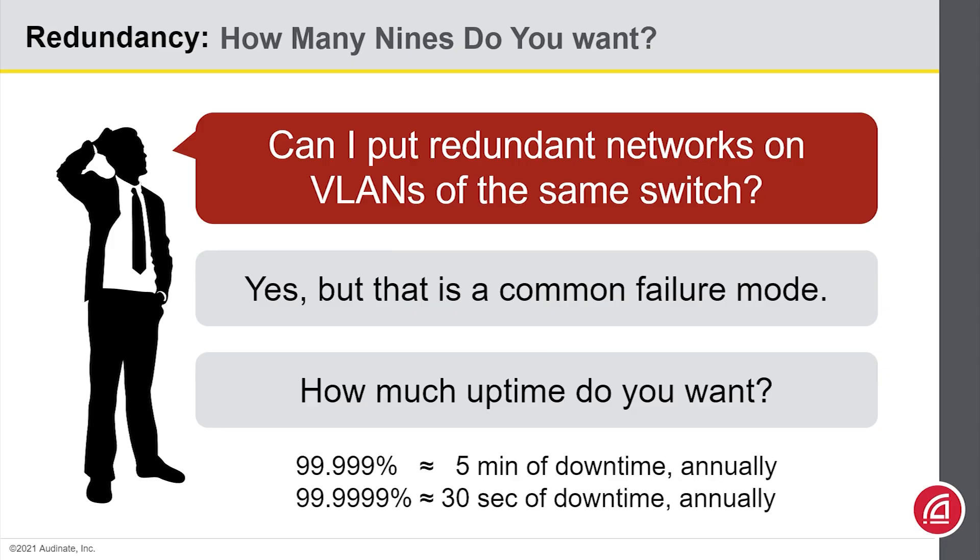Now, typically, the target is somewhere around five or six nines of uptime. And just to put that in perspective, five nines of uptime means you have about five minutes of downtime annually.